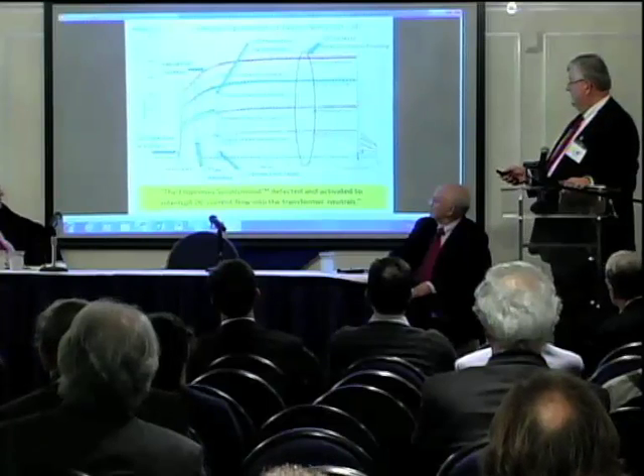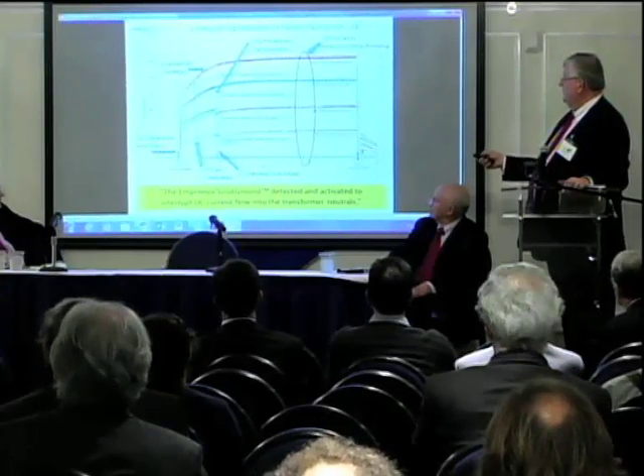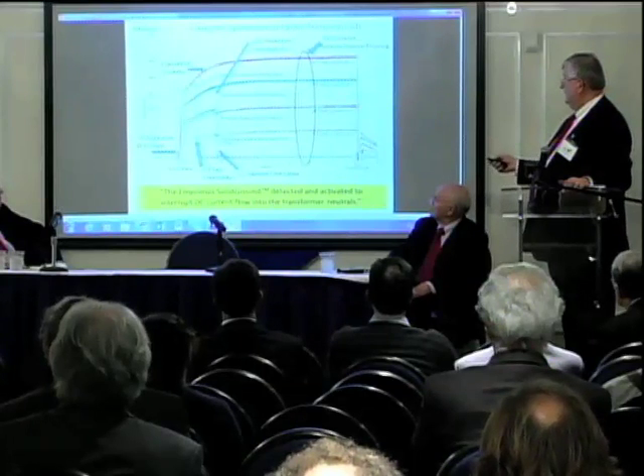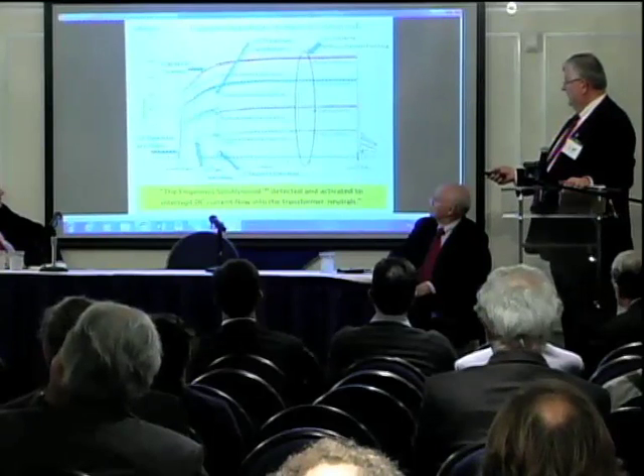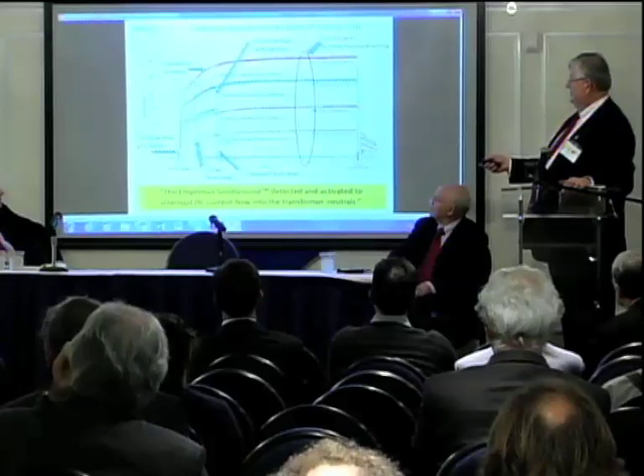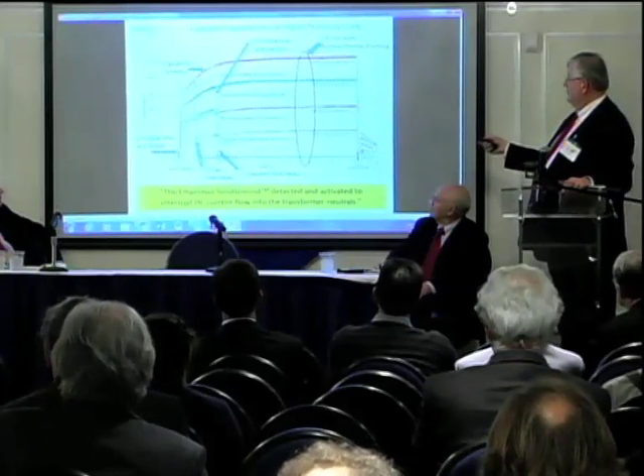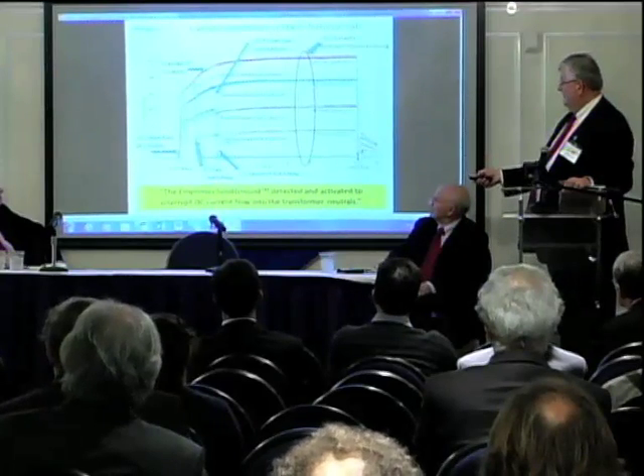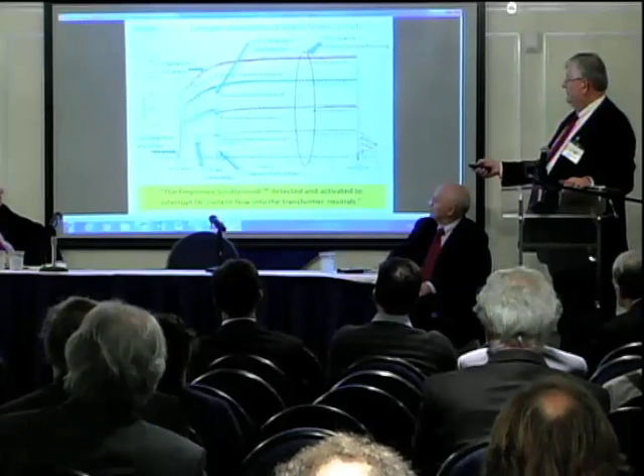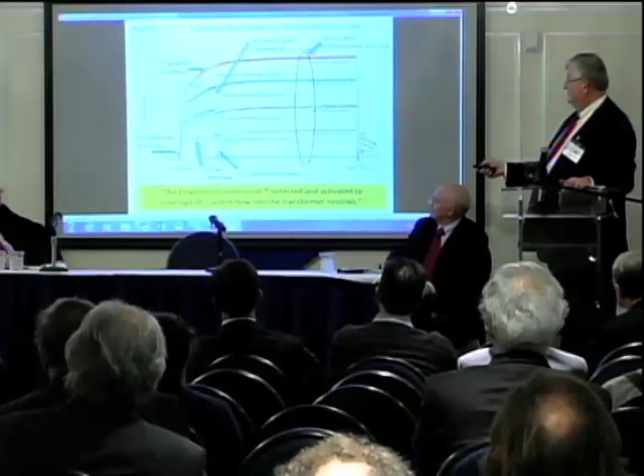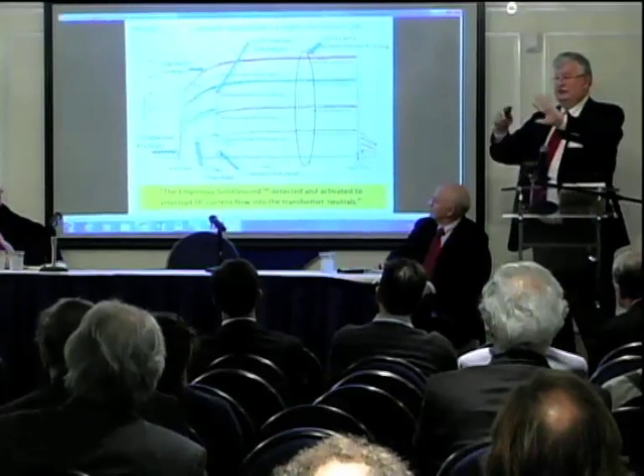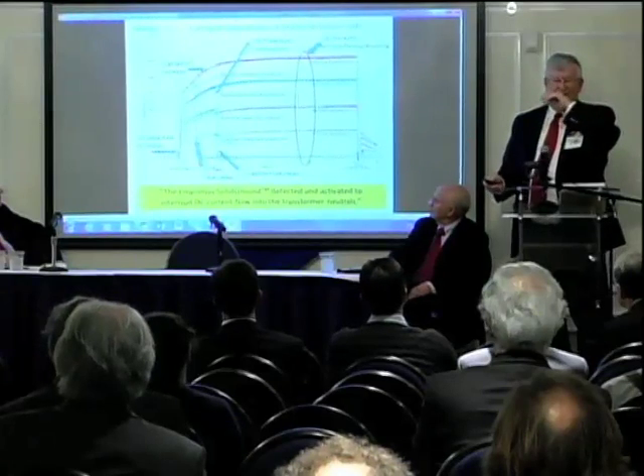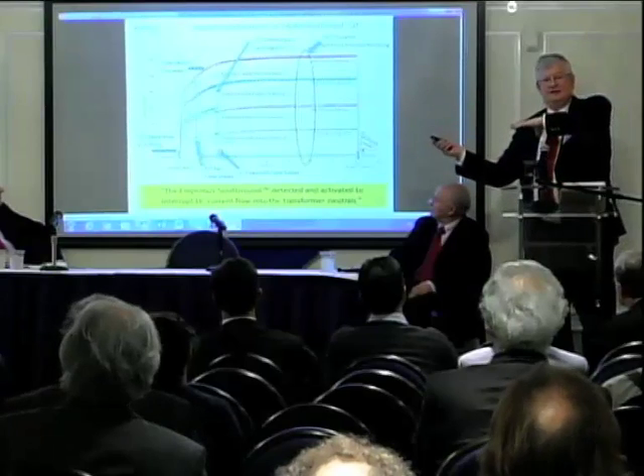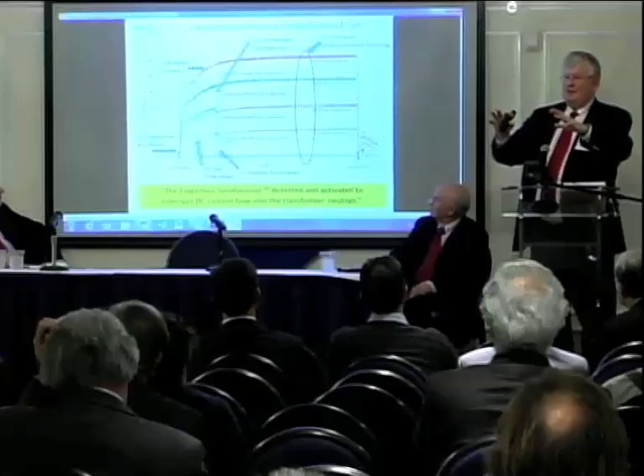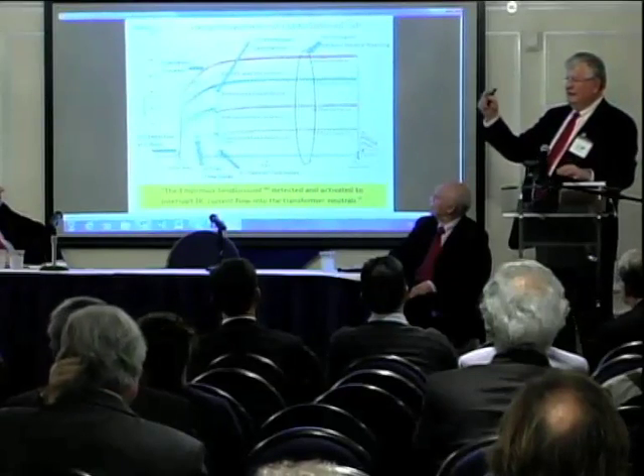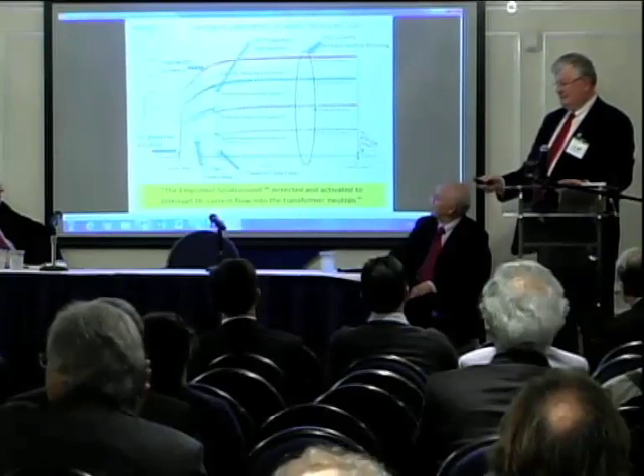In fact, here's a kind of a synopsis. These lines over here are with no blocking. So when there's current injection, DC current injection of different levels, you can see that here. That's what the curve would look like. But as soon as blocking was put in, and it was arbitrarily set at different time limits here, it immediately went to zero in every case where it was set and goes across. So it just stops the block, it stops that altogether. Our guys were out at the site, and when they were injecting DC, the transformer would be humming and shaking and noisy, and as soon as the blocking went in, it stopped, just like that.